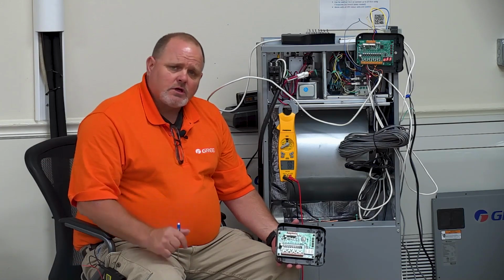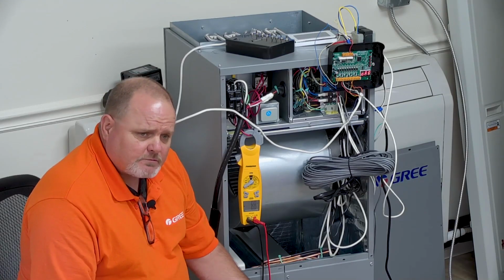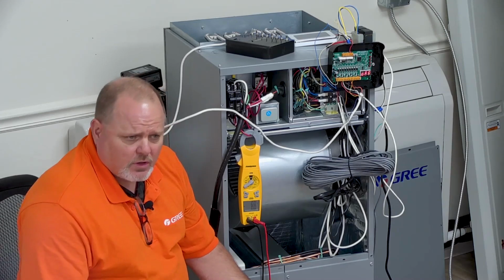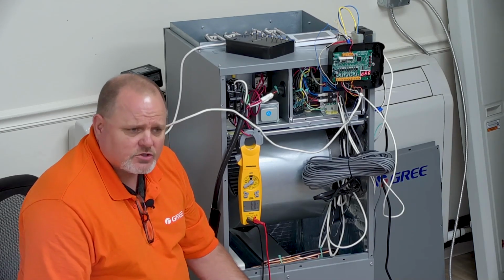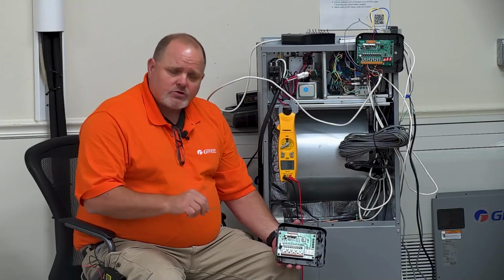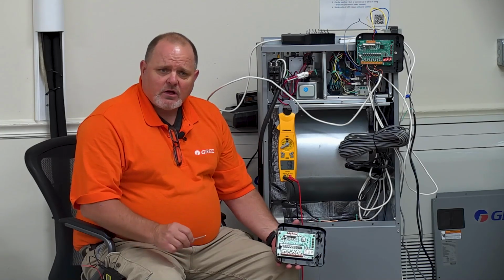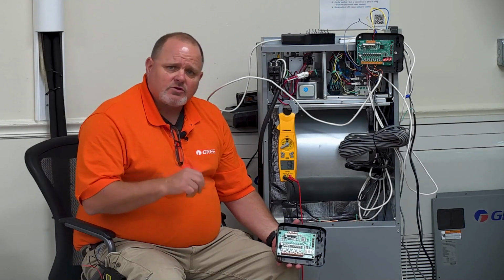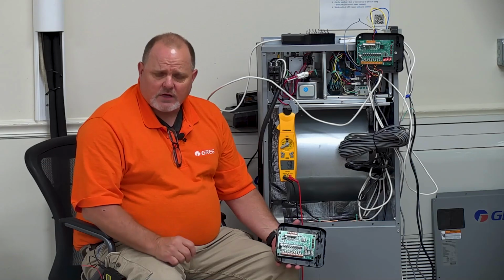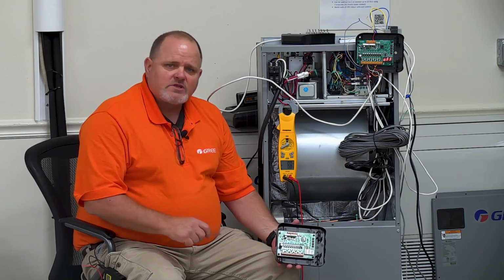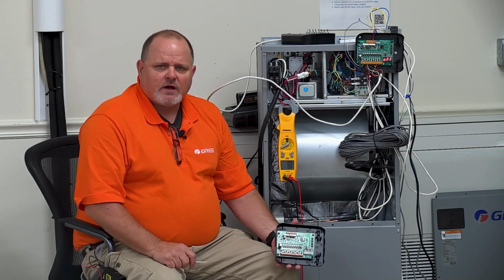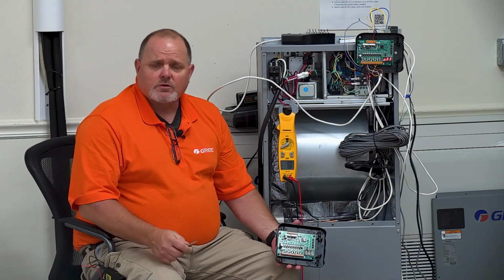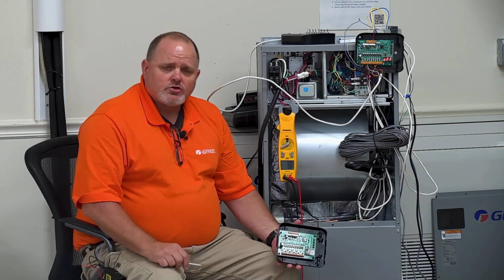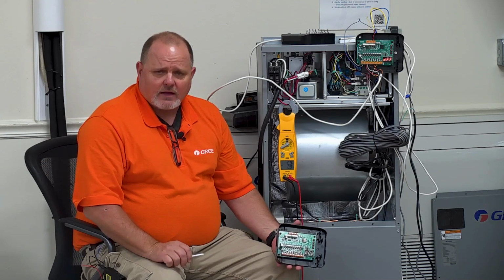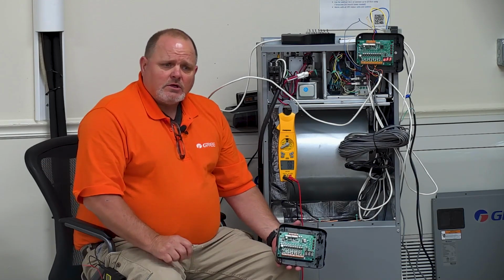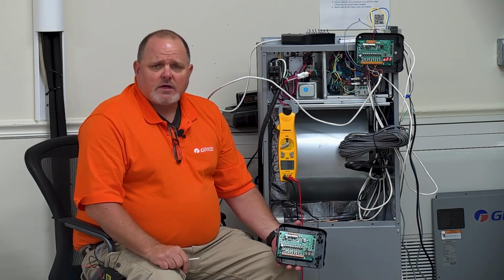So you are going to use a heat pump thermostat. And as you are well aware, a heat pump thermostat has an OB terminal. Just keep in mind that on most of those thermostats, the O and B is shared, and you have to set it up in the thermostat whether you want it to energize the reversing valve in heating mode or cooling mode. With GREE's equipment, we always energize the reversing valve in heating mode, which is typically referred to as the B terminal. And on this new 24-volt adapter, you will have exactly that. You will have a B terminal. And then we'll also have some electric heat connections and stuff.